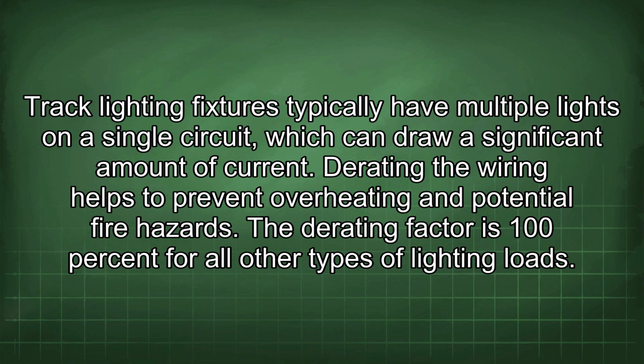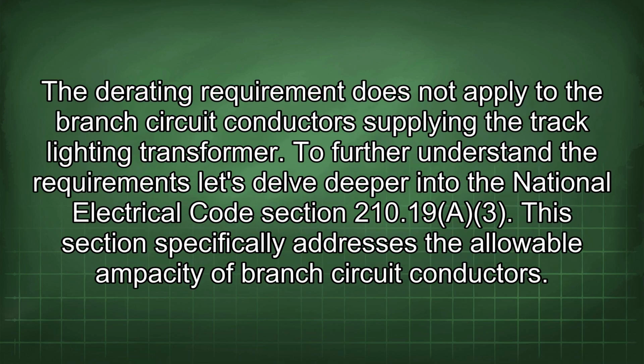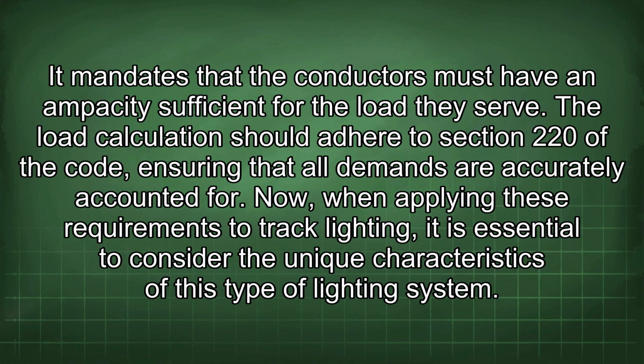The derating factor is 100% for all other types of lighting loads. The derating requirement does not apply to the branch circuit conductors supplying the track lighting transformer. To further understand the requirements, let's delve deeper into the National Electrical Code Section 210.19 A3. This section specifically addresses the allowable ampacity of branch circuit conductors. It mandates that the conductors must have an ampacity sufficient for the load they serve. The load calculation should adhere to Section 220 of the Code, ensuring that all demands are accurately accounted for.